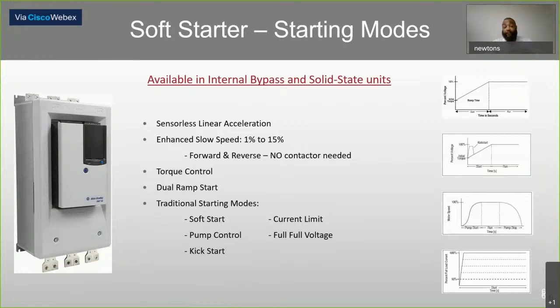So what are some of the advantages of doing those nice smooth starts? Well, one, it'll help the mechanics of your machine. Instead of having a very violent start going from 0 speed to full speed, especially if it has some heavy loading, or maybe some gearing on the back end or front end of that motor, the soft start will help ease the wear and tear on your mechanical hardware.